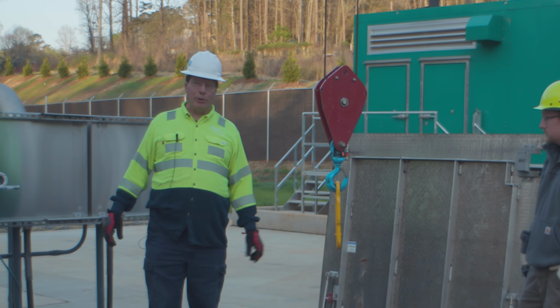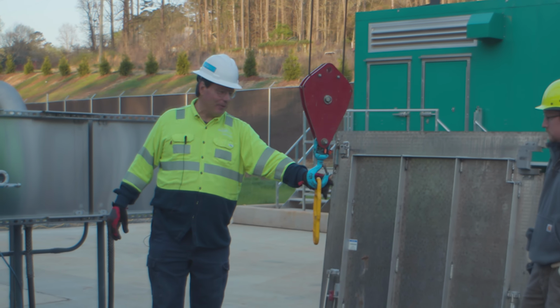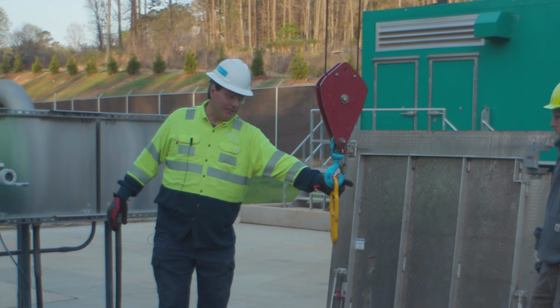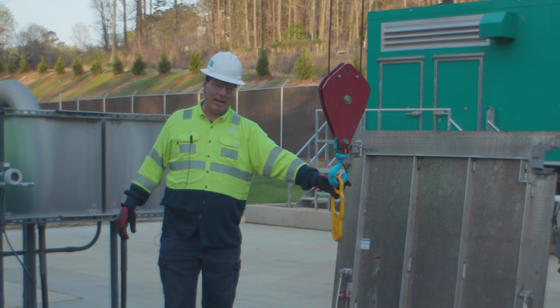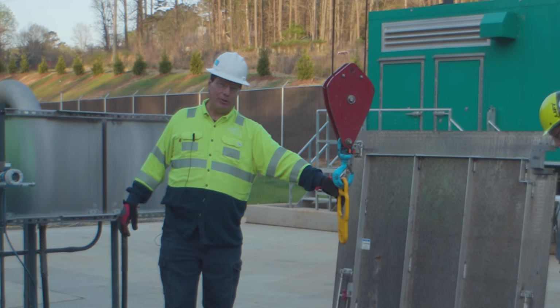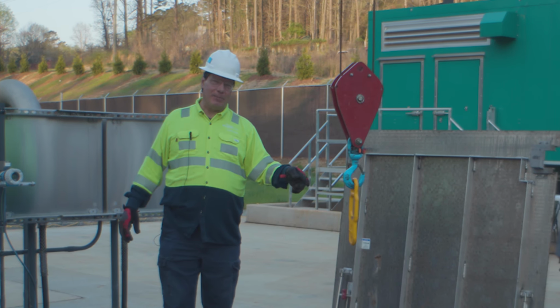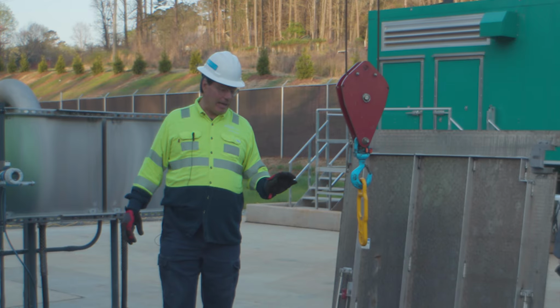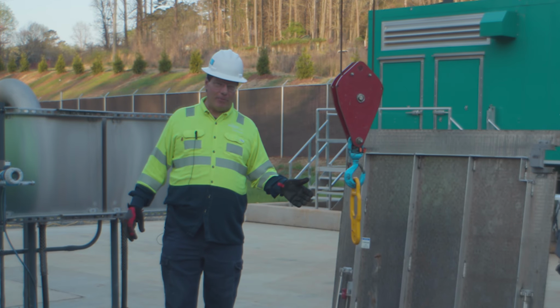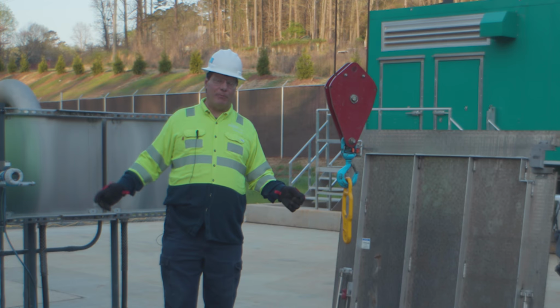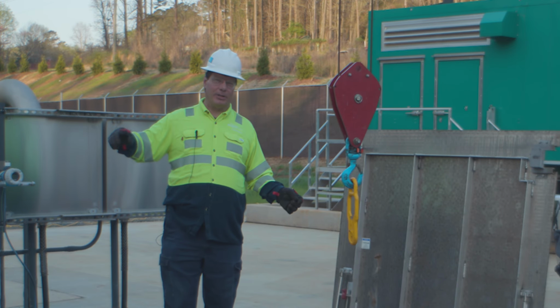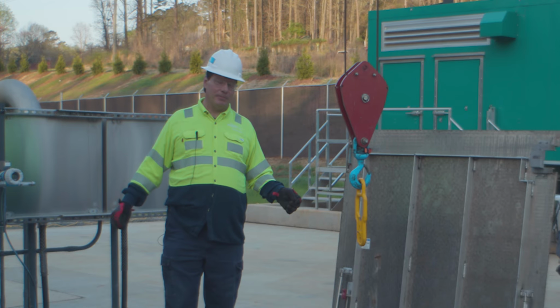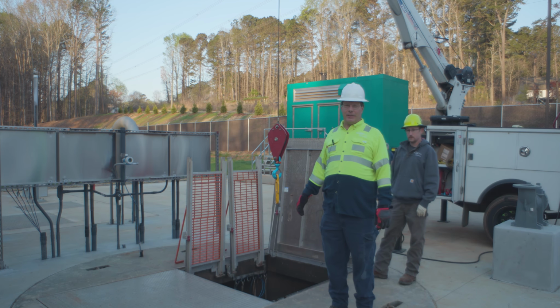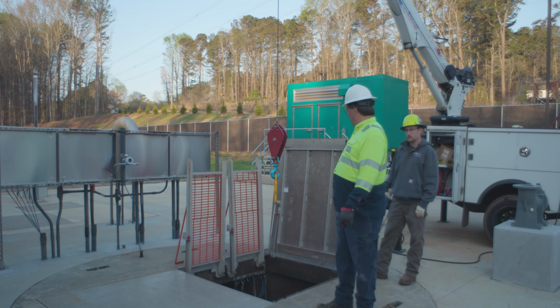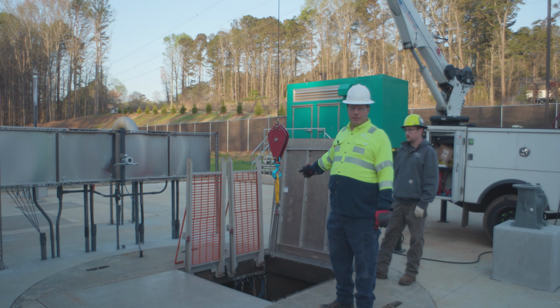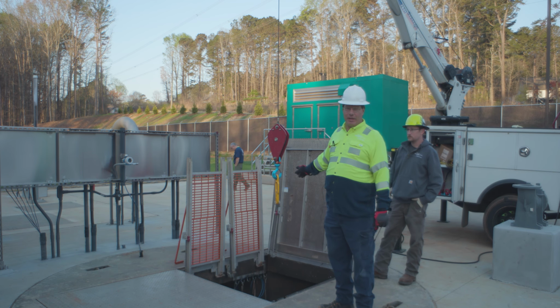We're getting ready to actually pull the pump. You can see on this example, this crane has a safety latch on it so that this can't fall off while we're lifting it up and down. We're going to hook it onto a rope, and you'll see that here in a minute after we open this hatch up. We're going to lower it down part way, and then we're going to take a video of what we have to do as far as turning off the breaker and the controls before we continue any further. We're going to hook up the rope connected to the chain sling before we go down and pull it through the grip eye that's connected to the crane hook.